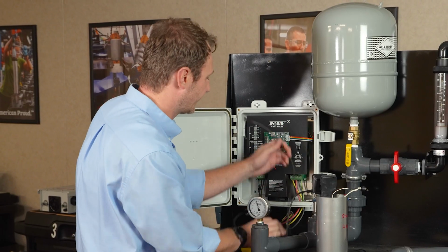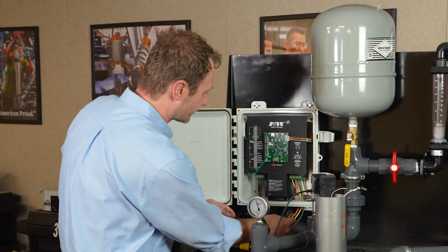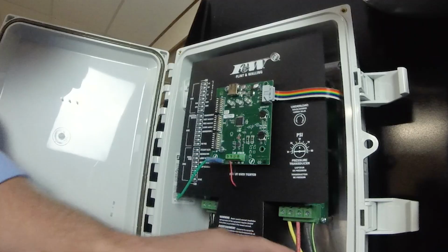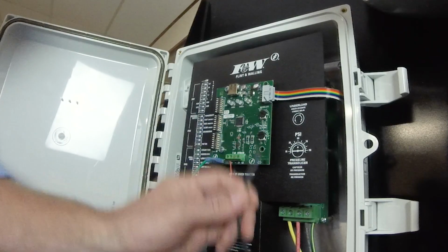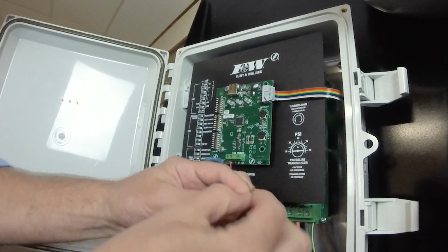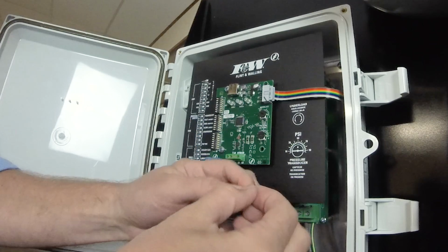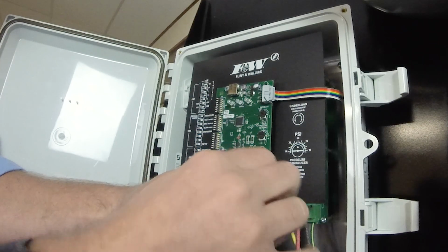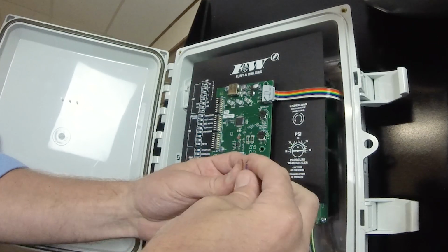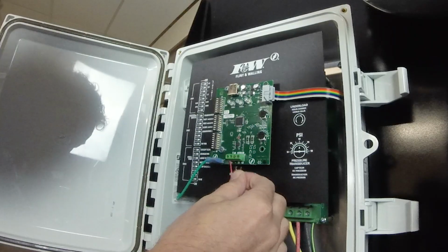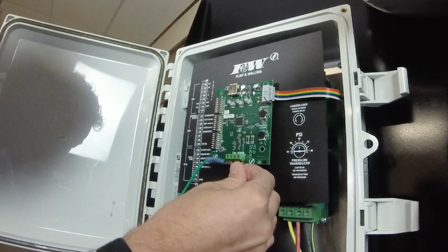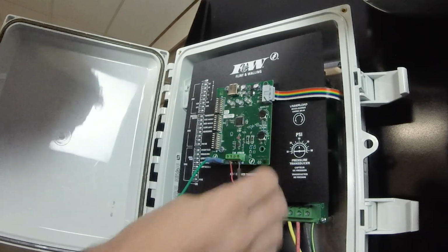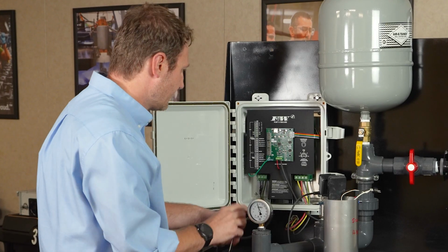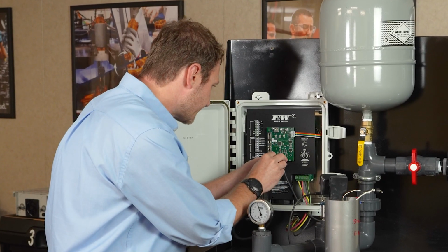Last thing we've got to put in here is our transducer wire here. So we're going to come up through the bottom. And we've got 2 leads on this transducer. And the brown we're going to throw into S1. And the blue is going to go into S2 right here. And we'll go ahead and tighten those down as well.